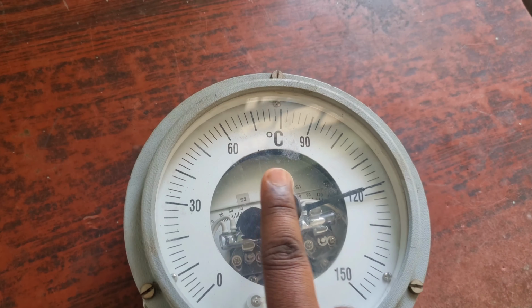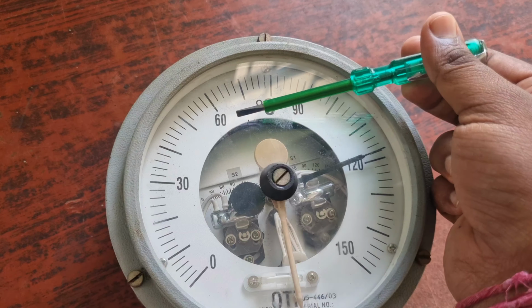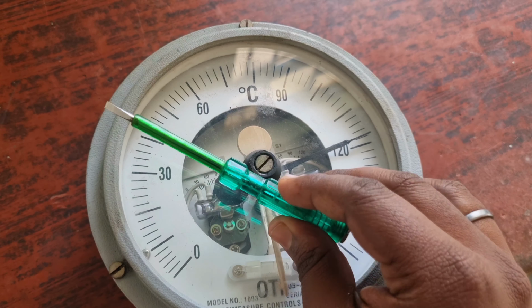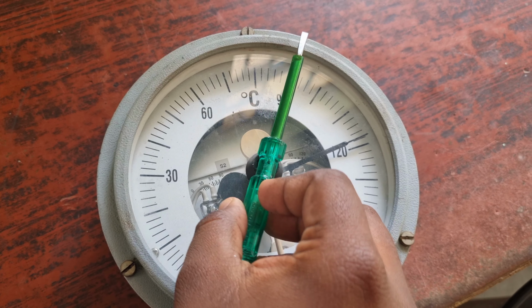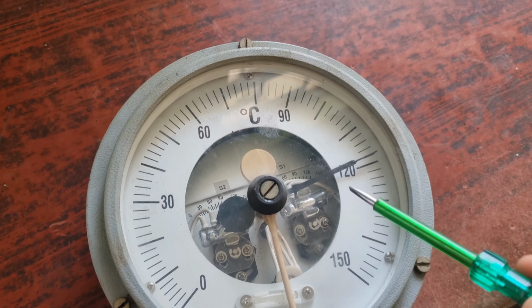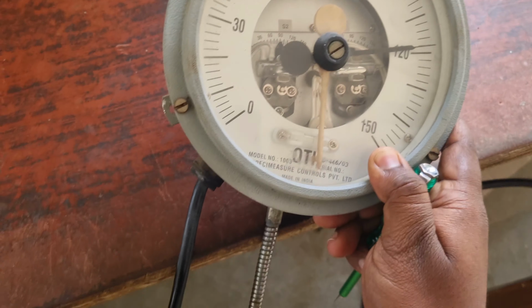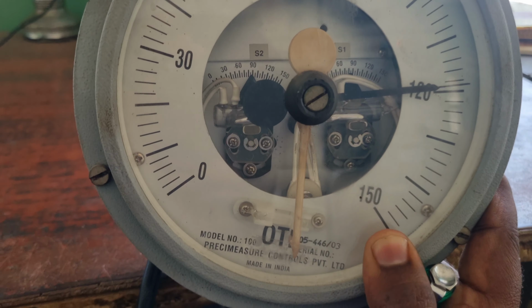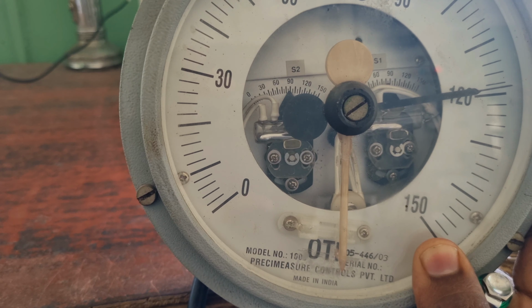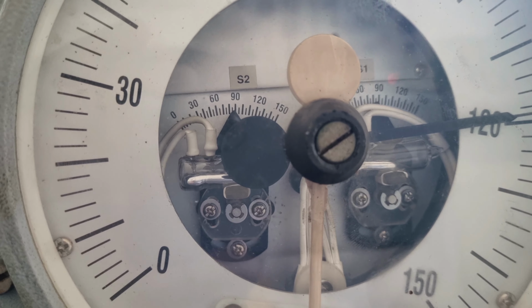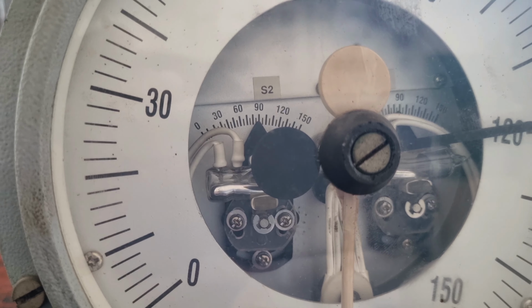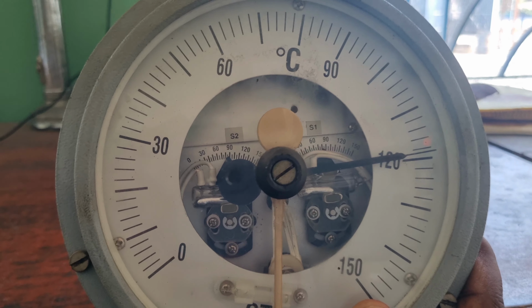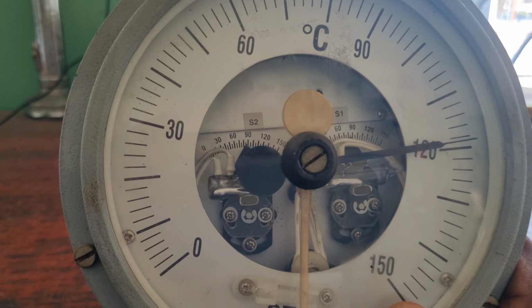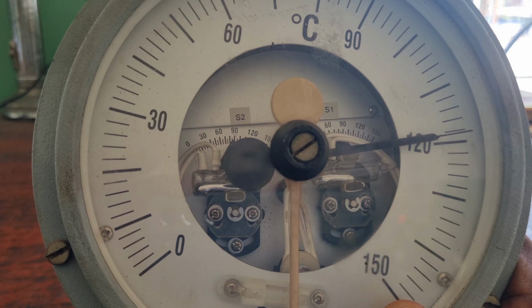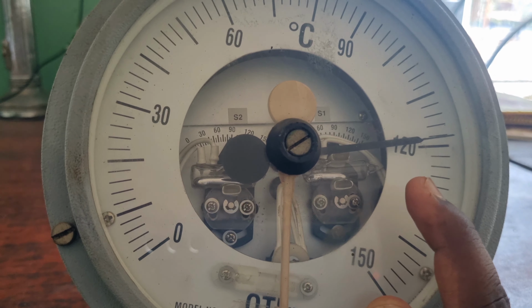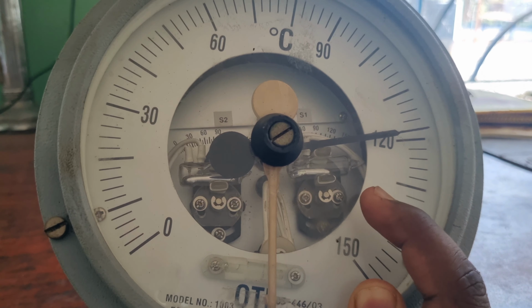When the needle moves towards any particular direction, let's say the temperature is slowly rising, when you set the preset, it will stay like this horizontally, and slowly the mercury inside tilts by the movement of the needle, thus closing the switching action. So one switch is on the left side and one is on the right side, one for alarm and one for trip.